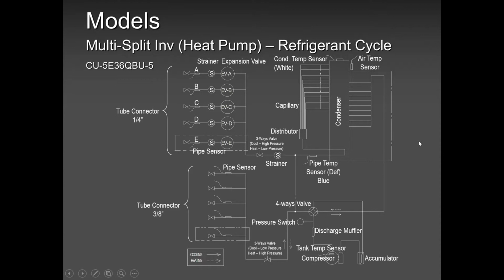So in most cases, it's very easy to troubleshoot a multi-zone, because if all indoor units are not working, all indoor units are flashing, definitely the problem is outside. But if 1 out of the 4 or 1 out of the 3 or 1 out of the 2 is flashing, definitely it's the indoor unit that has a problem. Very rare it's the outdoor problem. Very, very rare.